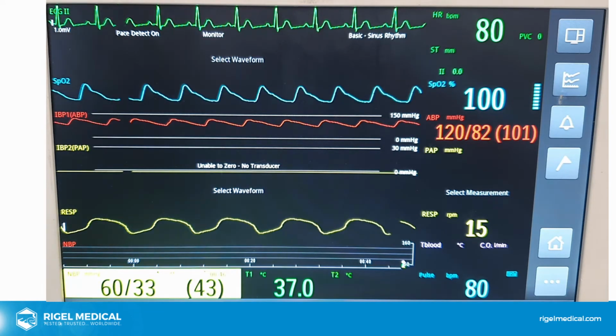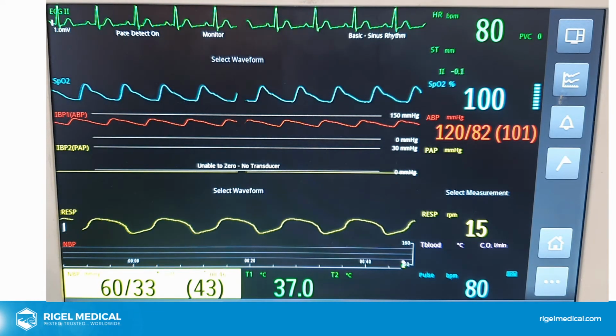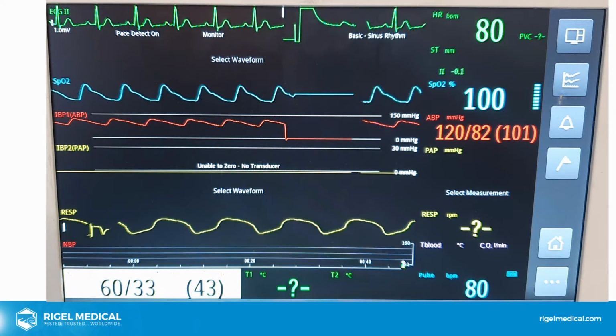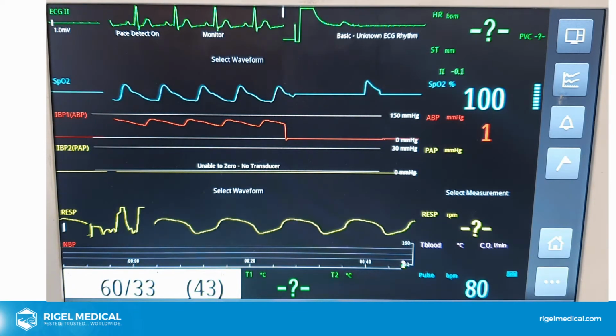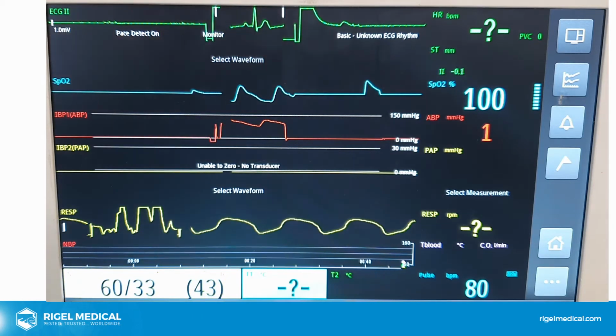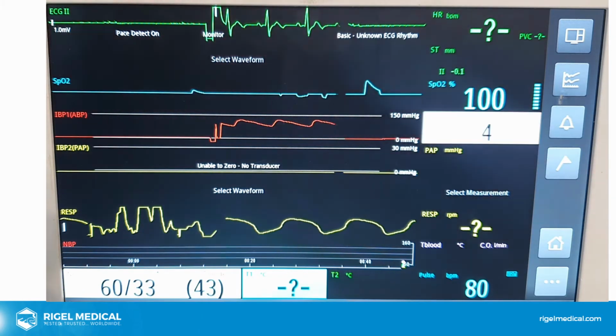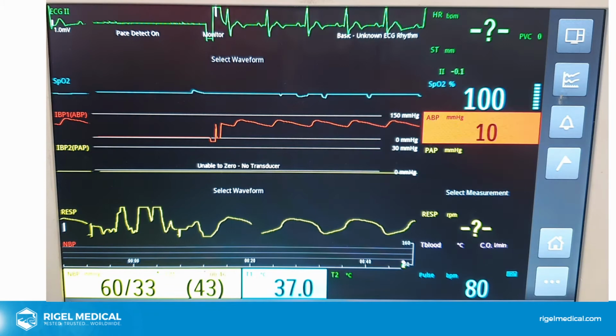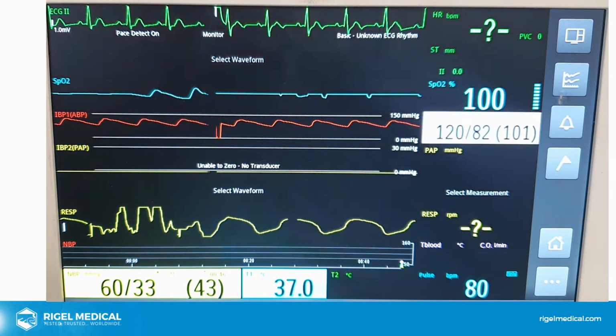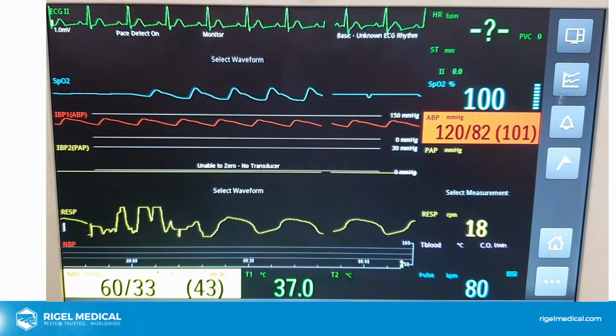So all the values are close to as expected. Diastolic is slightly high on both IBP and NIBP, but for the specification of this monitor would be within spec. In terms of NIBP, I spoke before that it's purely for repeatability and not for accuracy. Static pressure tests, which we do in service modes, test the accuracy of the monitor itself. So in terms of repeatability, if you're getting the same results, then this is a reading to be expected.